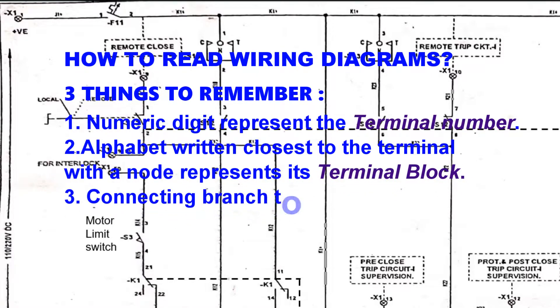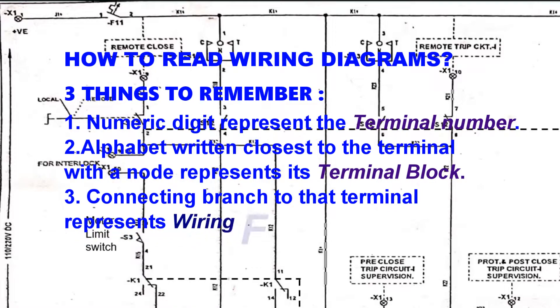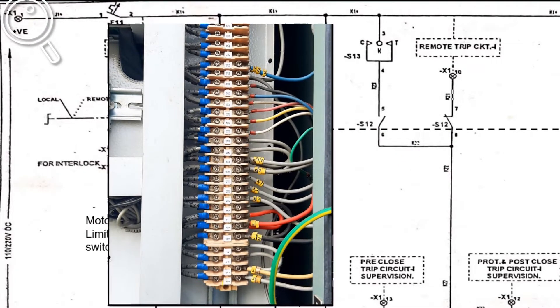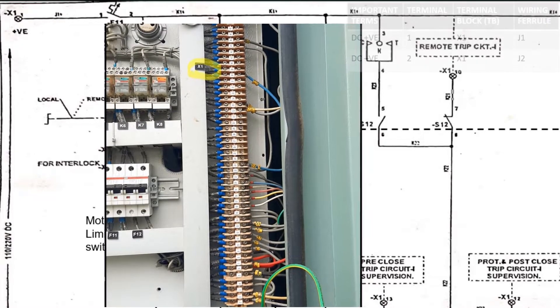Let us start and closely look at the top left of this network diagram. Always remember three things. First, the numeric digit shown always represents the terminal. Second, the alphabet written closest to the numeric digit represents the terminal block. And last, the connecting branch of the network represents the wiring ferrule. From this, we can say that DC positive is given on terminal 1 of the X1 terminal block having wiring ferrule J1.